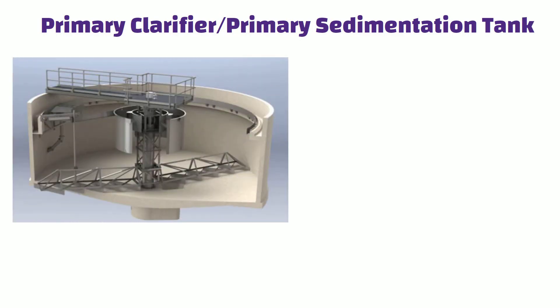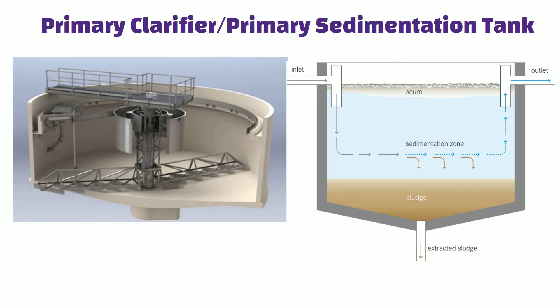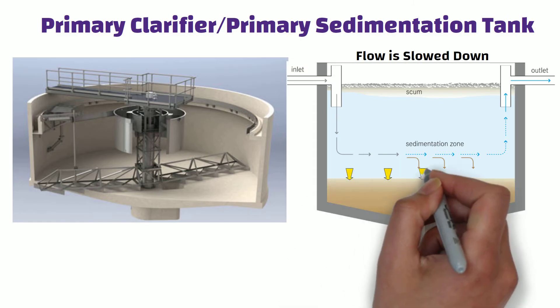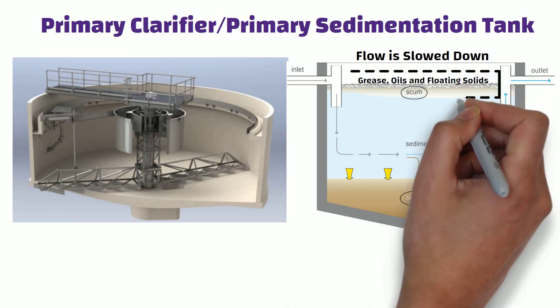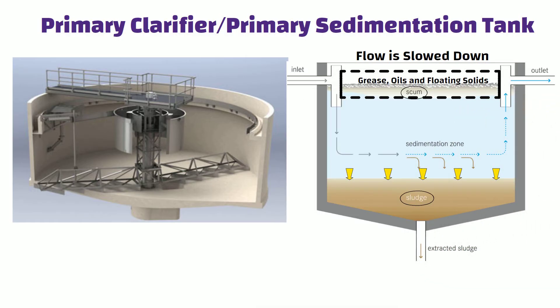Primary Clarifier or Primary Sedimentation Tank: the waste water enters the primary clarifier after passing through screening and grit removal. The flow is slowed down, allowing settleable solids to sink to the bottom of the tank — this solid material is called sludge. Grease, oils and other floating solids rise to the surface, forming a scum layer, which is continuously removed by a skimming mechanism. The sludge accumulated at the bottom is collected using a sludge scraper.